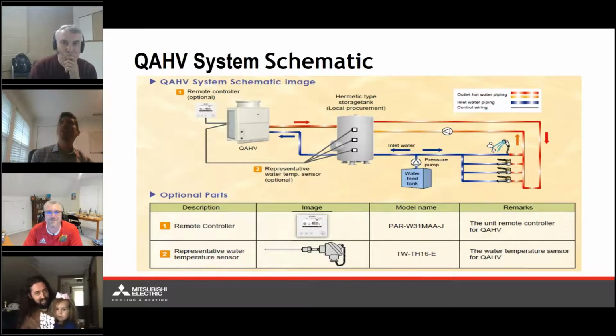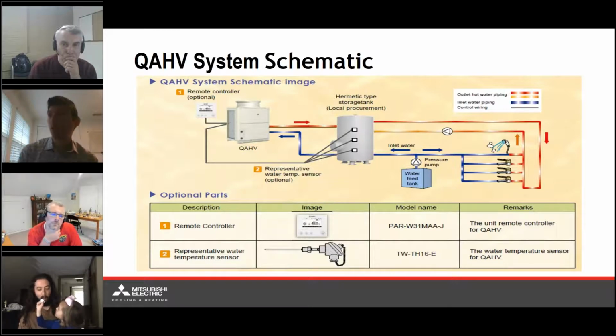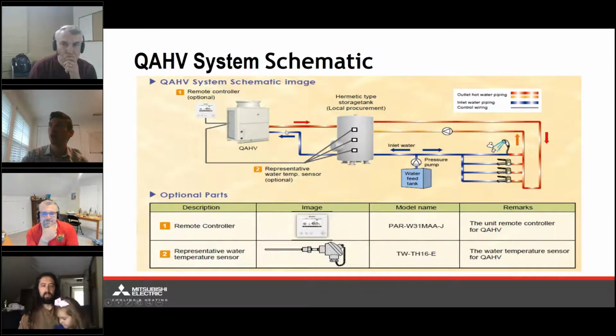All right, so here is a system schematic for a 3-sensor temperature control. What we're looking at here, and remember the QAHV is a self-contained unit, so all the piping that we're seeing here is water piping, with no refrigerant piping external to the unit. So we're going to be producing this hot water in the unit itself and sending it to a hermetic type storage tank.